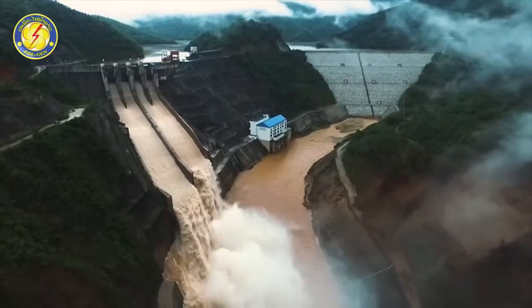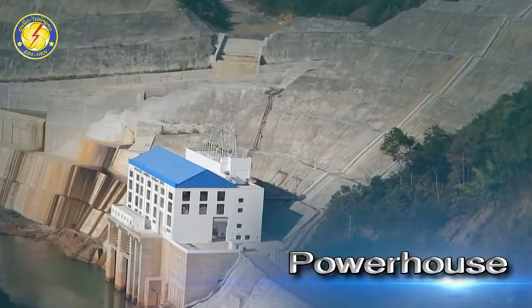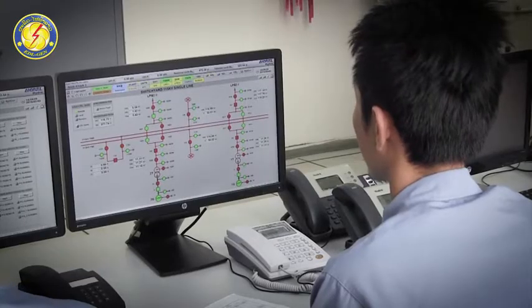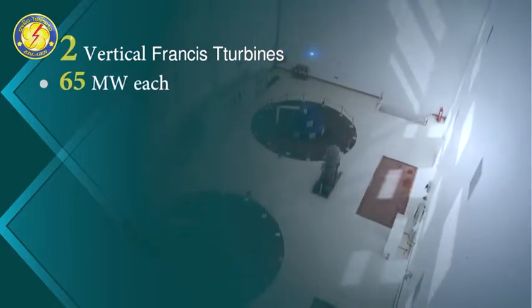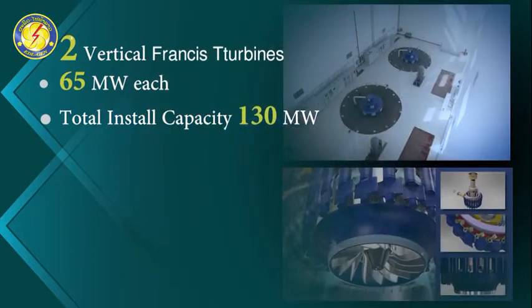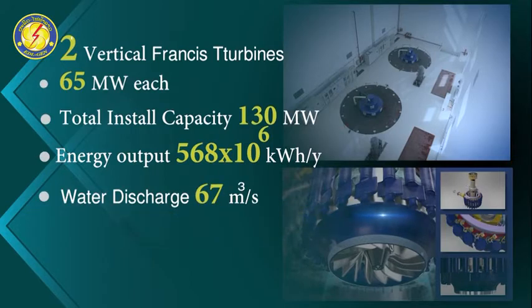The design head is 111 meters high. The powerhouse consists of a control room with 2 units of vertical Francis turbines at 65 MW each, giving a total installed capacity of 130 MW and an annual average electricity production capacity of 568 million kWh per year. The water volume through each turbine is 67 cubic meters per second.